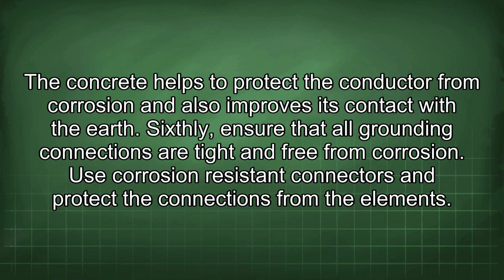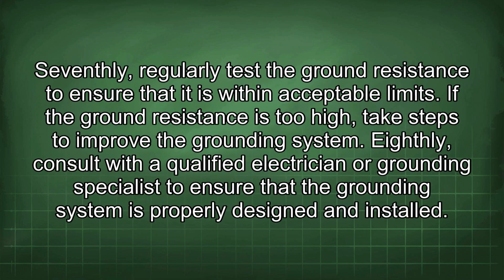Sixthly, ensure that all grounding connections are tight and free from corrosion. Use corrosion-resistant connectors and protect the connections from the elements. Seventhly, regularly test the ground resistance to ensure that it is within acceptable limits. If the ground resistance is too high, take steps to improve the grounding system.